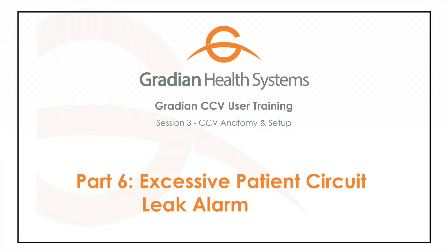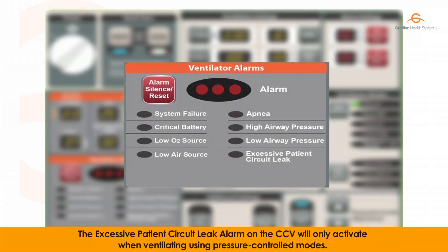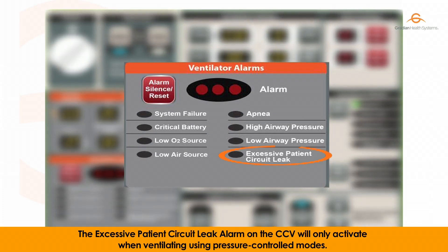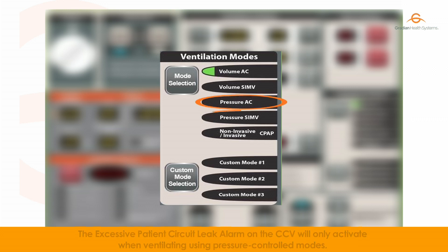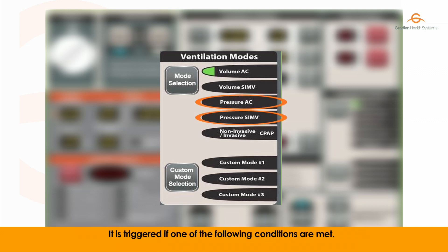Excessive Patient Circuit Leak Alarm. The excessive patient circuit leak alarm on the CCV will only activate when ventilating using pressure control modes. It is triggered if one of the following conditions are met.